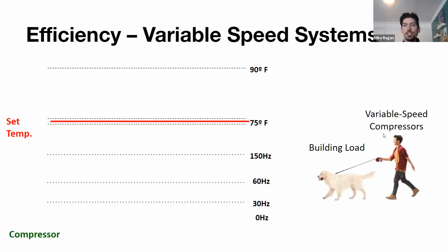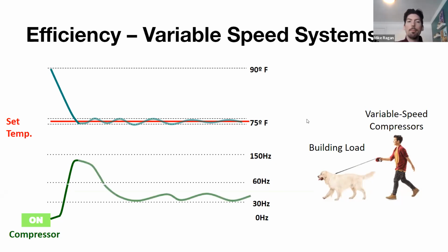We're going to start off in the same situation. We're starting at 90 degrees, where we're going to bring the system on. So the compressor turns on, we're going to lower that temperature, and instead of just outright turning off the compressor for this system, it's instead going to ramp down. So that's where that variable speed comes into play. If we're able to ramp down the compressor speed, we're going to have a much, much tighter deadband around that 75-degree set point. So this is going to be you in control of this walk, and the dog is walking along with you. You're in control of the temperature of the space. You're not reacting to massive, massive fluctuations in the temperatures in the conventional speed systems.